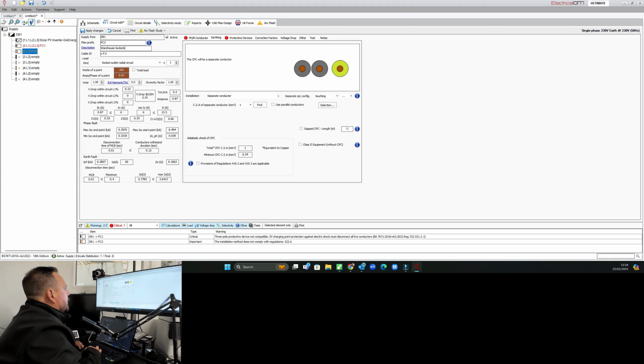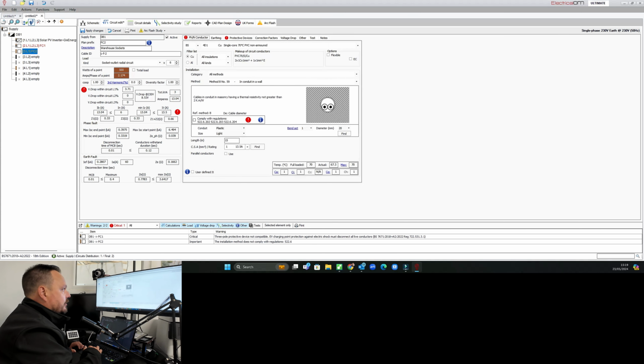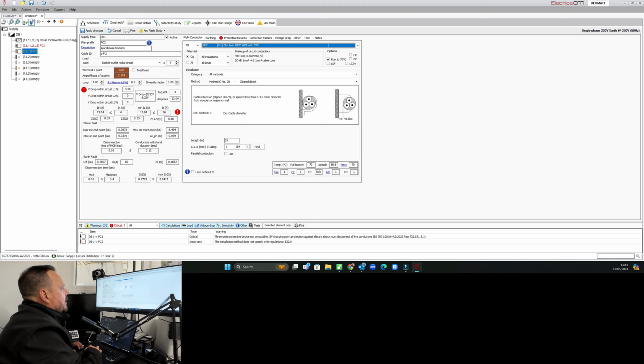Really simple installation here. We'll say on this one we're going to 200 watts is probably okay for a domestic environment, but they're going to use a little bit more here. We'll pop it at 500 watts for each socket outlet, and they've got 6 sockets for want of a better example. And if we go back to our phase neutral conductor, again, in this case, we're going to be using LSF. So this is flat twin 90 degree. So we'll pop that on there and we can run that to 70 degrees again.